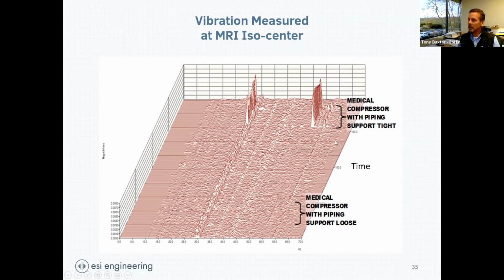One isolator that probably cost $30, and it would have taken the contractor 10 minutes to put in, was the cause of that high vibration. And I think they were happy they spent the $250,000. They saw the value of all those isolators in these measurements.